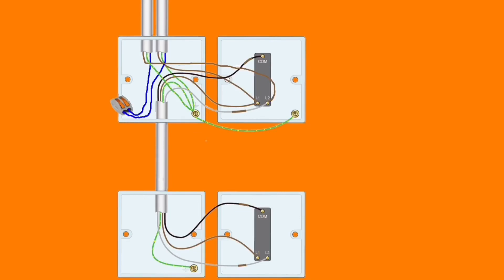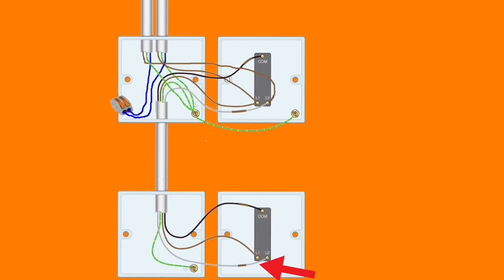We've introduced the three-core from the top switch to our new switching position. Both switches are now two-way switches, and the connections in the bottom switch are black for common identified with brown sleeving, with the brown conductor and gray conductor identified with brown sleeving into L1 and L2 - it doesn't matter which way around. We've now achieved two-way switching of our lighting circuit.